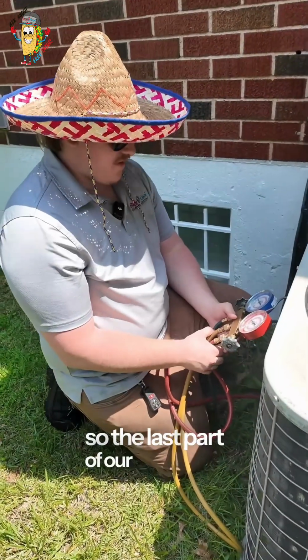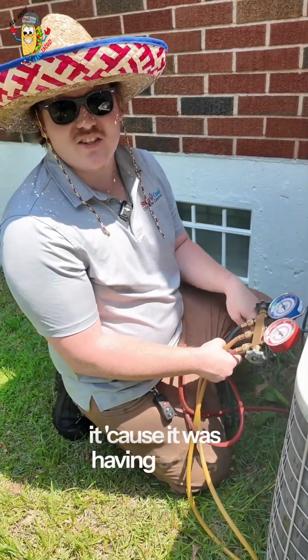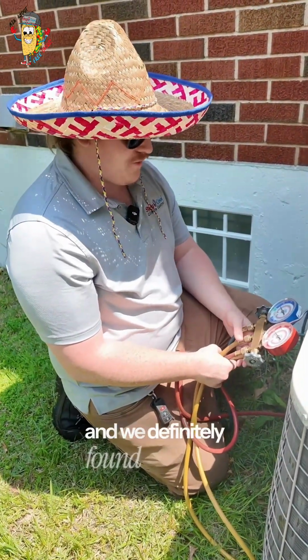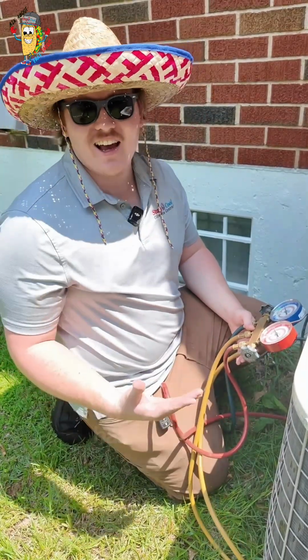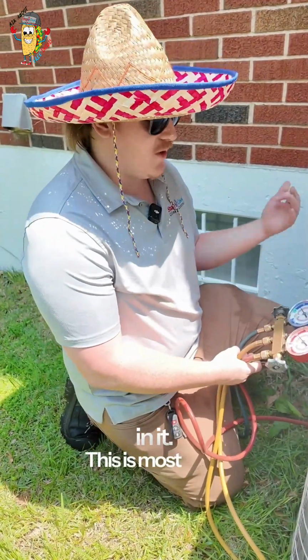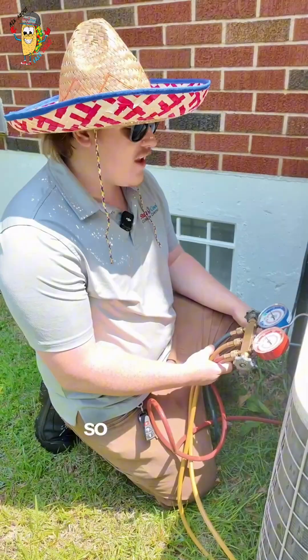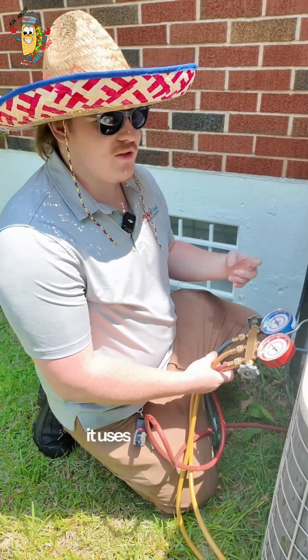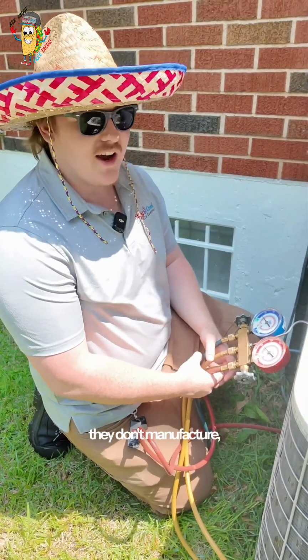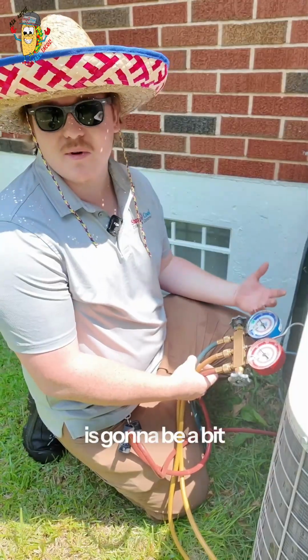Okay, so the last part of our inspection, we're putting some gauges on it because it was having some issues cooling, and we definitely found the cause of our issue. It basically has very little refrigerant in it. This is most likely because there's a leak in it somewhere. So with it being 22 years old, it uses the outdated refrigerant they don't manufacture. So this unit working is going to be a bit of a challenge.